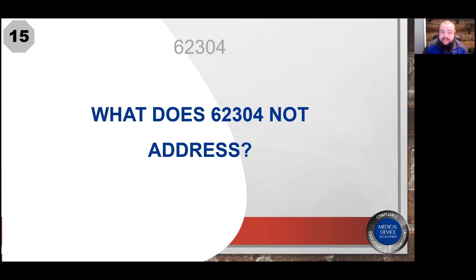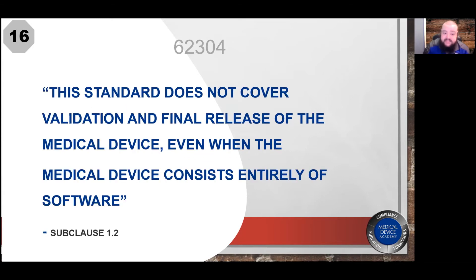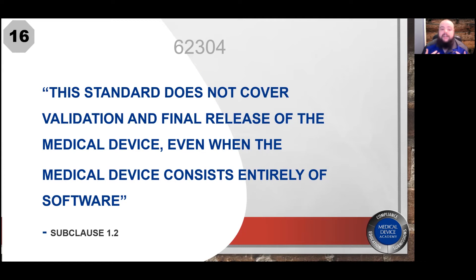But what does the standard not address? 62304 specifically does not get into validation and final release of your medical device, even if you have a standalone device or software as a medical device, and that comes straight from the standard itself in sub-clause 1.2.